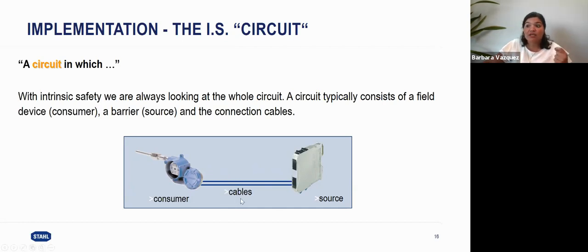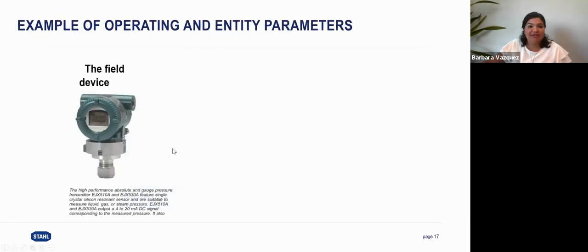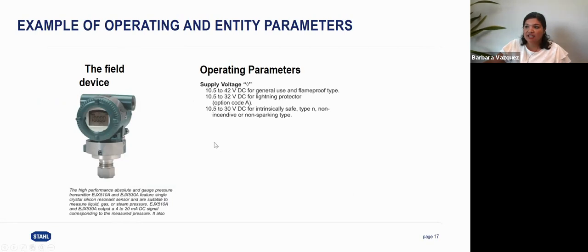Something important is that we need to do that loop verification. Obviously, we need to make sure the IS barrier will energize the field device and it will be working, but we also need to make sure we create that IS loop. So how do we create it? Let's go with a real life example. We have this pressure transmitter. It is a 4-20 device. On the data sheet, we see that it has operating parameters. It requires at least 10.5 volts and up to 30 volts to work properly.